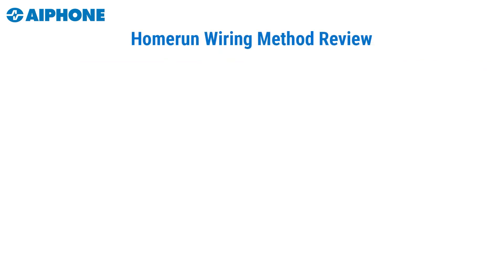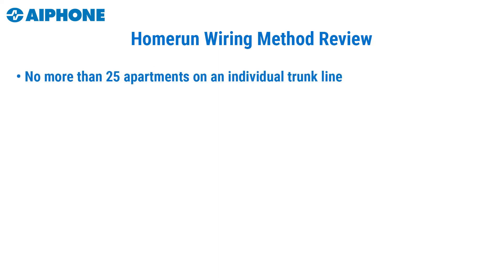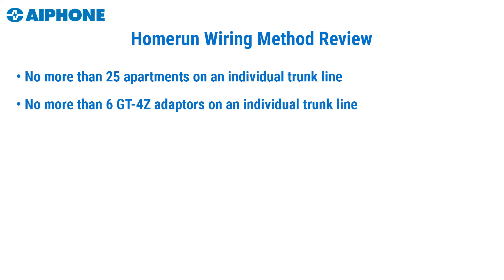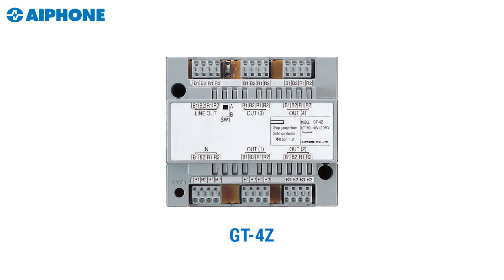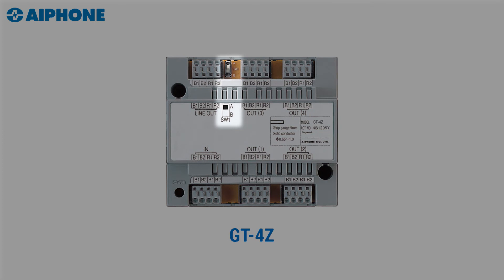To review: you cannot exceed more than 25 apartments or six GT4Z units on one trunk line, and you cannot have more than 48 apartment stations connected to a set of GTBC and VBCs. If you follow these guidelines you should be all set. Once you've added your last GT4Z on a specific trunk line, that GT4Z must be terminated by turning the switch AB to the A position.